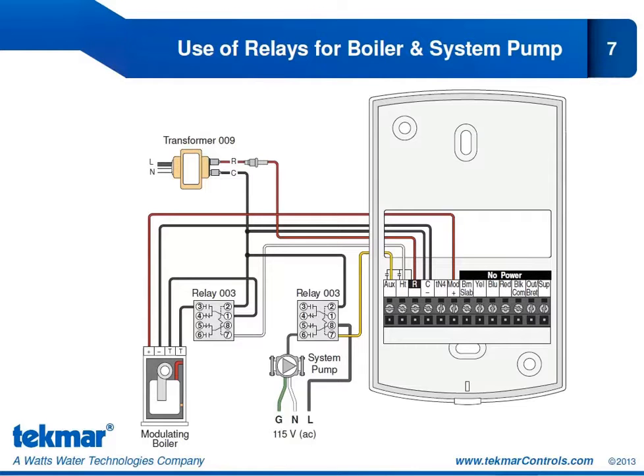Now I did mention the use of relays if we're doing a boiler enable and operating a system pump, and I wanted to show you this slide to make sure it's well understood why that's necessary. As we mentioned, the heat relay and the auxiliary relay are both tied to the 24 volt R. If we are requiring a boiler enable signal, as shown here, we of course want a dry contact. We don't want a wet contact, which we don't have. So we're going to connect a wire from the heat relay to the isolation relay 003. And the other side will go back to C. And that way, whenever that heat relay closes, we have a dry contact enable signal to our boiler.